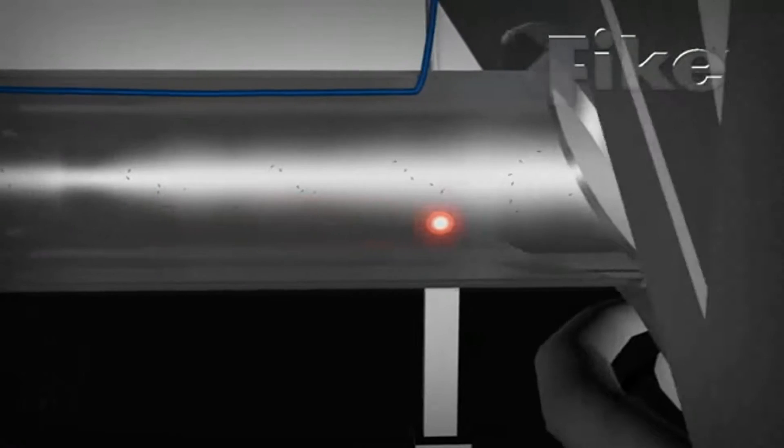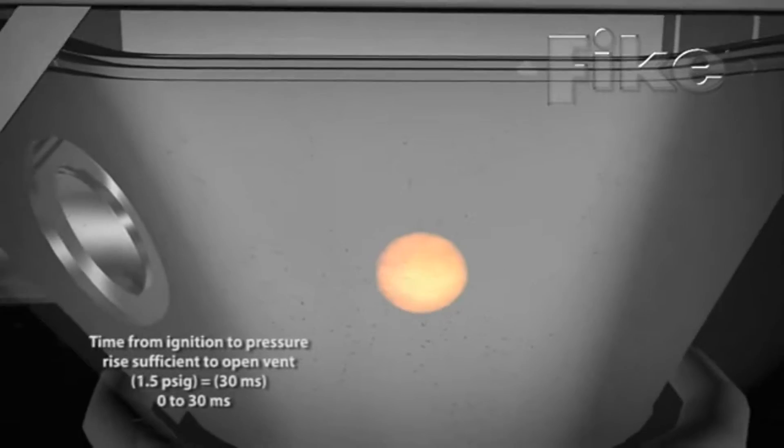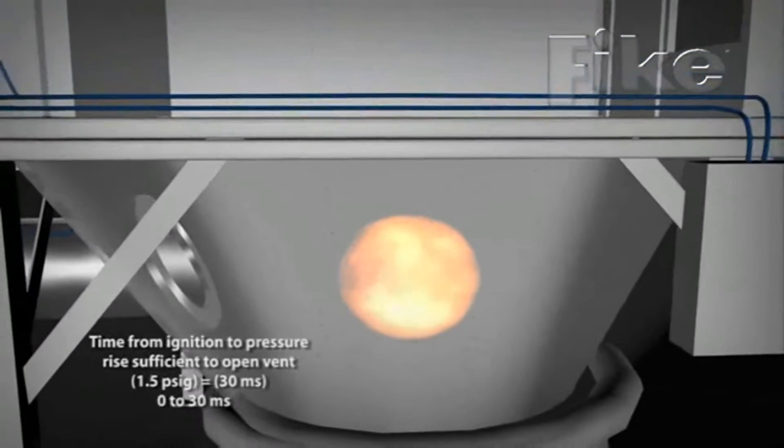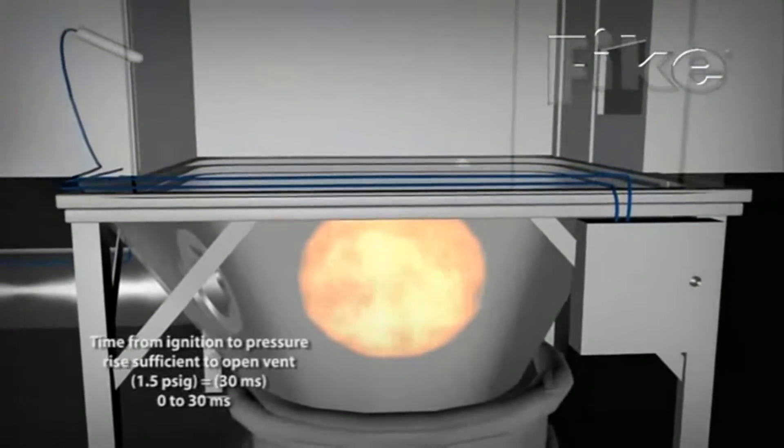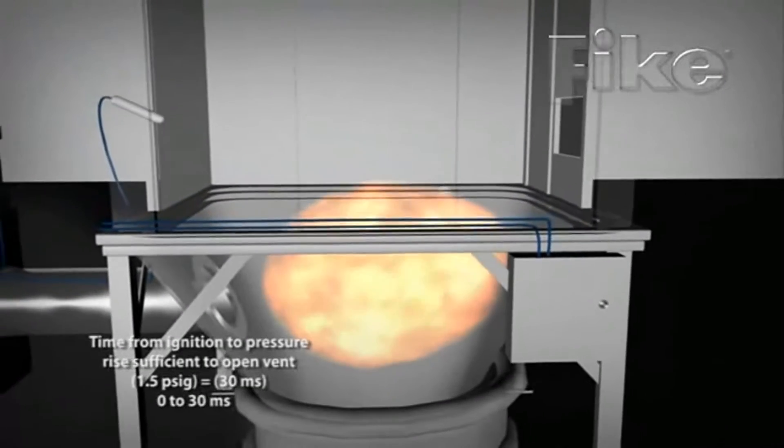When a spark or other ignition source ignites particulate in a vessel, a fireball develops as material burns and grows at an exponential pace. The pressure front expands as the fireball grows, reaching the explosion vent.